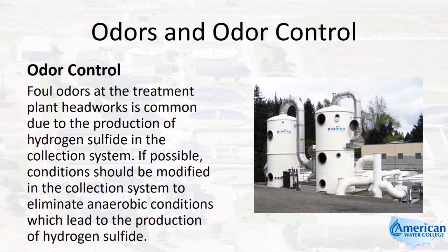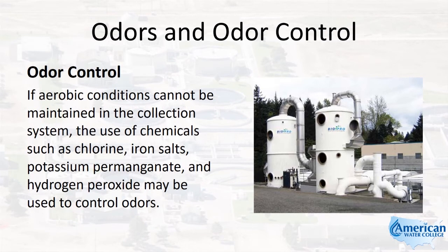Foul odors at the treatment plant headworks is common due to the production of hydrogen sulfide in the collection system. If possible, conditions should be modified in the collection system to eliminate anaerobic conditions which lead to the production of hydrogen sulfide. If aerobic conditions cannot be maintained in the collection system, the use of chemicals such as chlorine, iron salts, potassium permanganate, and hydrogen peroxide may be used to control odors.